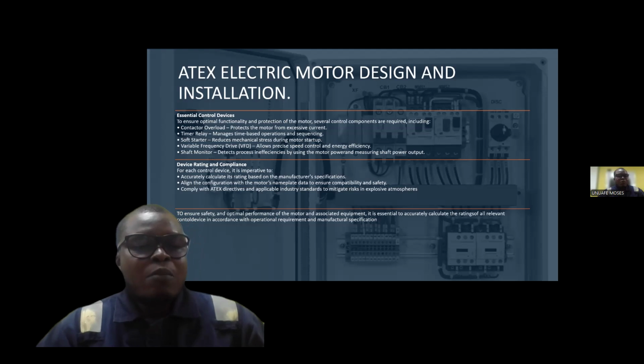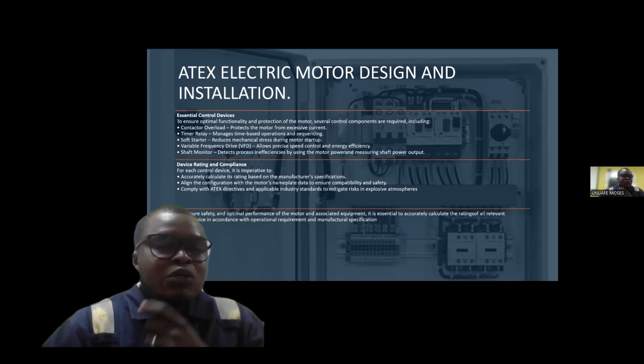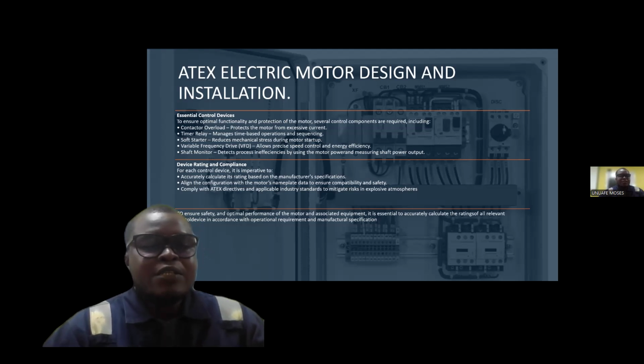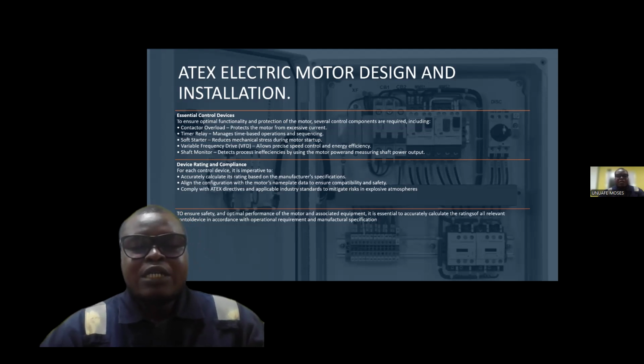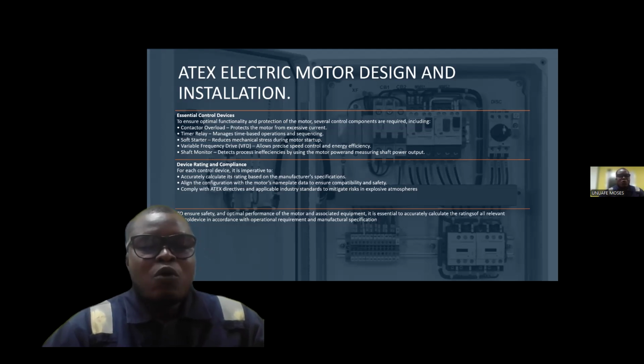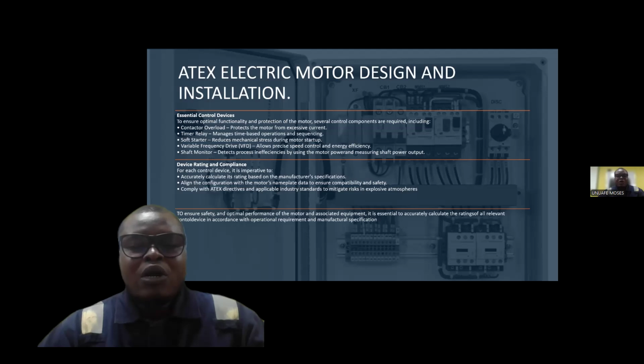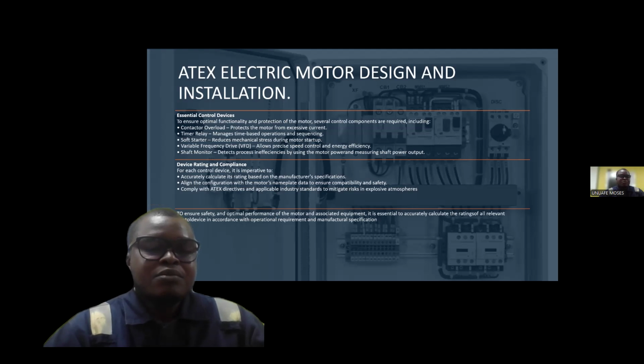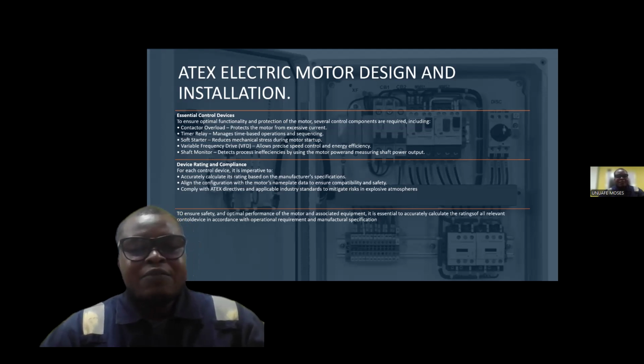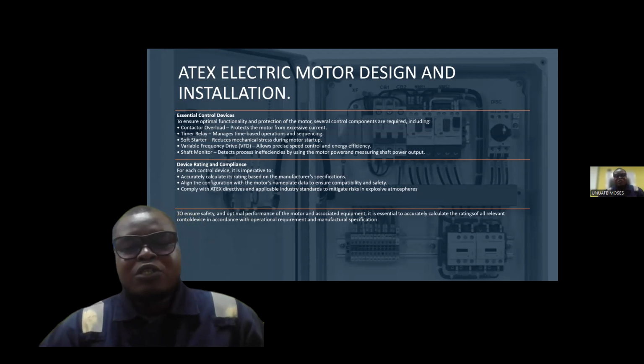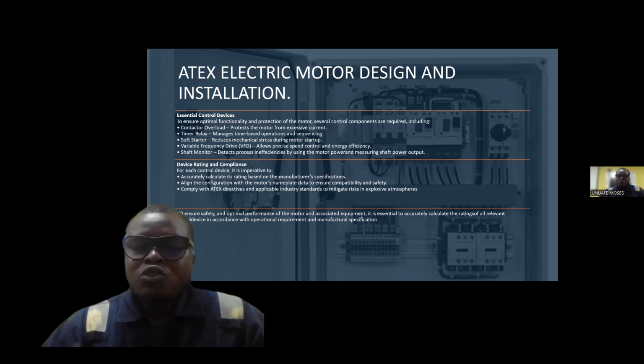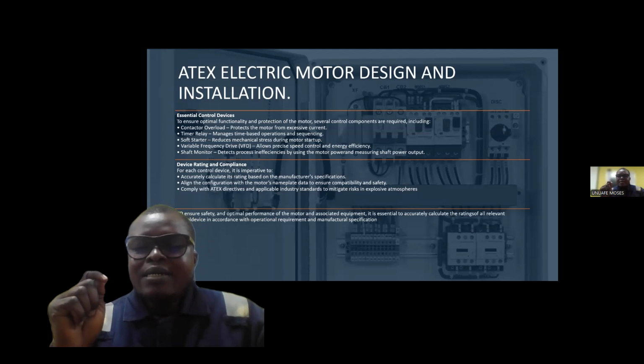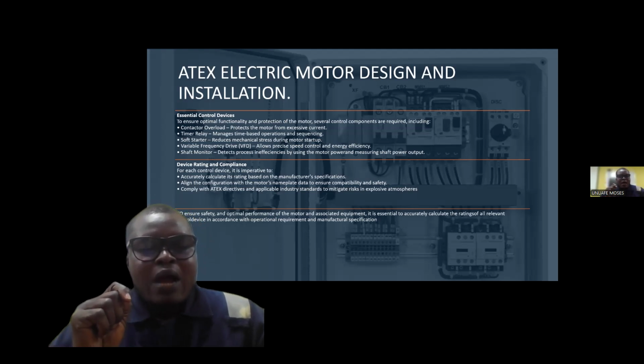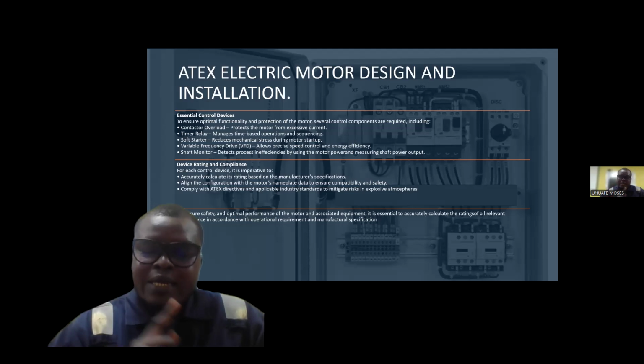And device rating and compliance will not be left out. For each control device, it is imperative to calculate accurately its rating based on the manufacturer's specification and align it with the motor nameplate data to ensure compatibility and safety, and also to comply with the Atex directive and applicable standards to mitigate risk in explosive atmospheres. Now, to ensure safety and optimal performance of this motor and associated equipment, it is essential to accurately calculate the relevant control devices according to operational requirements and manufacturing standards.